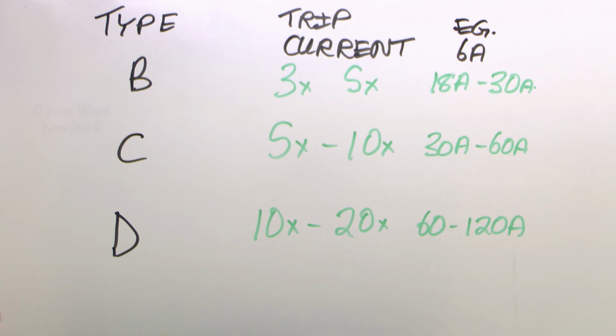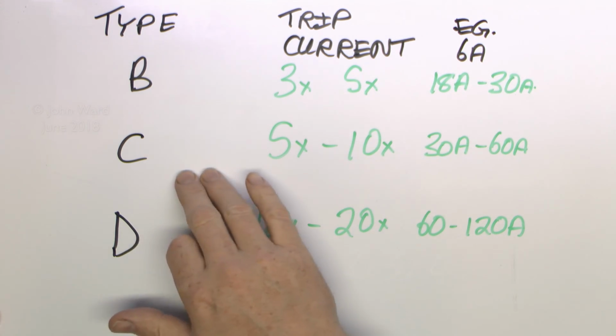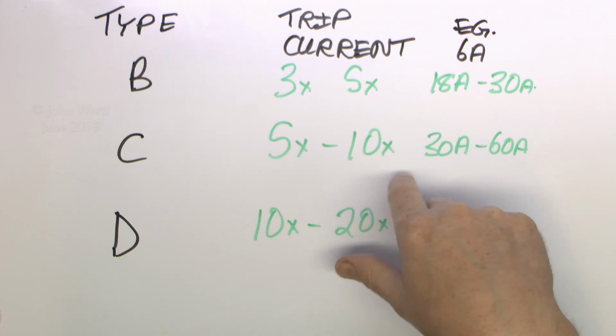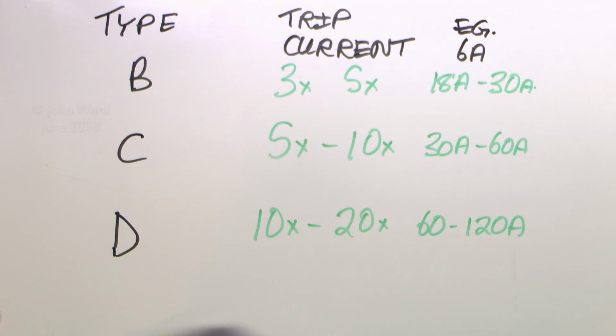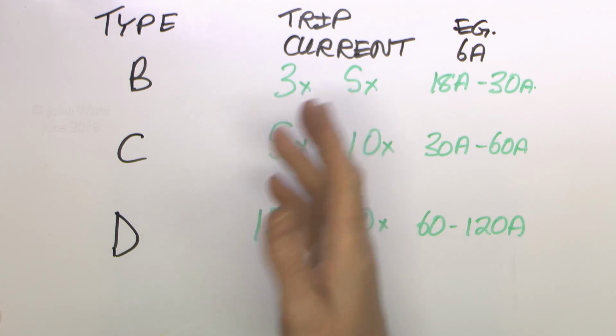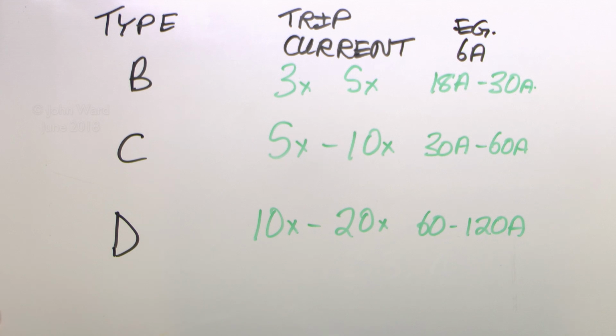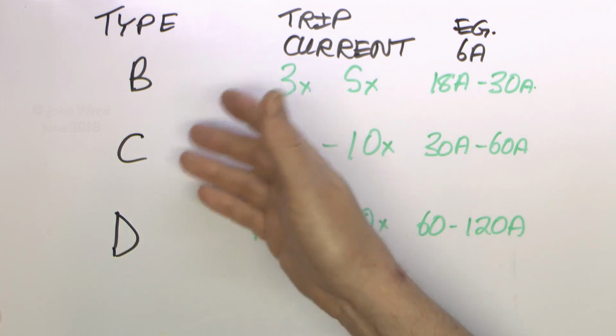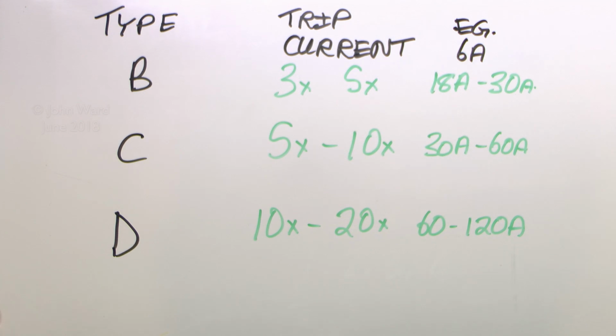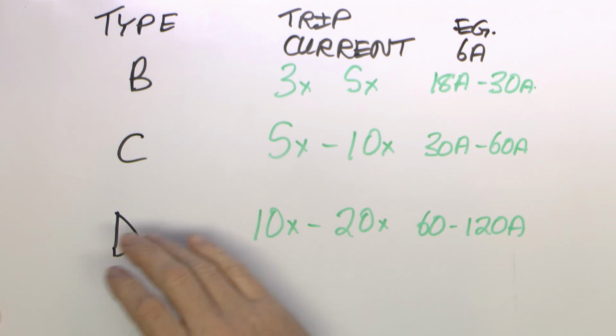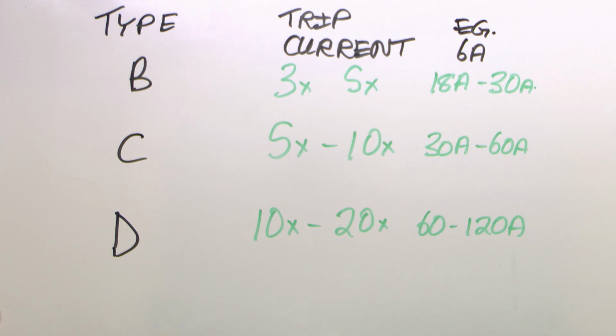and again the Type D may be required there. Now we'll often see Type C sold as motor rated, but that's not really true at all. It just happens that the current they trip at is larger than the Type B. They may well be used for motors quite often, but they can be used for plenty of other stuff as well. And in some cases it may not be appropriate to use a Type C for a motor, you may need a Type D instead, or in other cases a Type B may do just fine. So just because they're sold as motor rated, it does not mean that, oh, you've got a motor, shove a Type C on it automatically. Same as it doesn't mean, oh, we've got a welder, bung a Type D on, because again there are other things to consider.